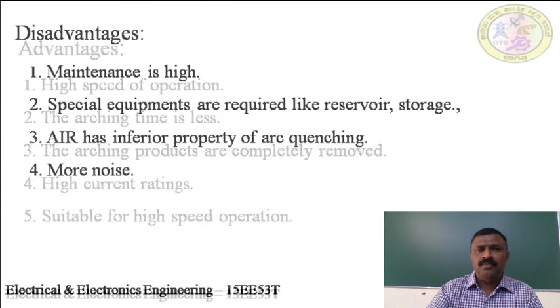At the same time, you have a few disadvantages. One, maintenance is always high. Second, it needs special equipment like a reservoir for storage of high pressured air. And air has the inferior property of arc quenching because the dielectric strength of air is less, so hence it is referred to as an inferior property. And of course, during the operation of an air circuit breaker, it will produce more noise.